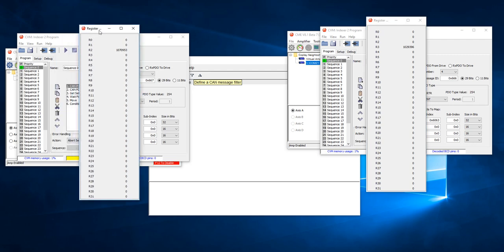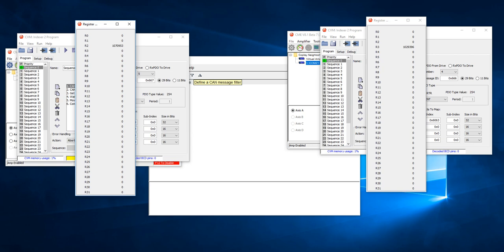Let's just quickly go through some prerequisite information. So this again is for CANopen drives, not EtherCAT drives, and this is a firmware feature, and this is only for plus products. So starting with firmware 4.12 or greater for the plus firmware, or it's also an ARM firmware, so 1.56 ARM firmware or higher, you'll have this CVM feature. So it adds options to the network options parameter. It adds a feature to that. So you set the network options parameter to hex 30 in RAM and flash, and then you'll enable this feature.